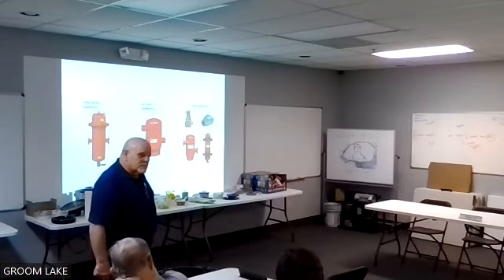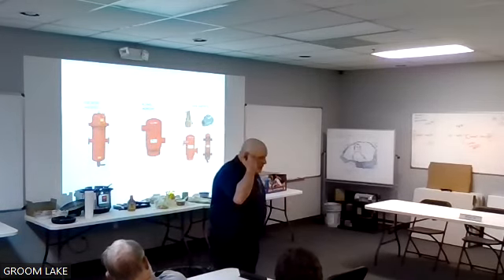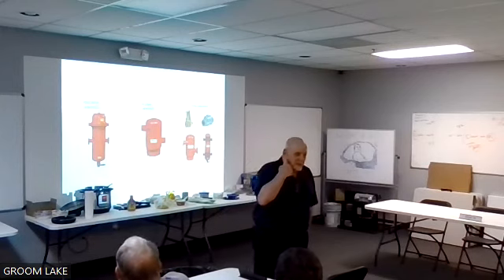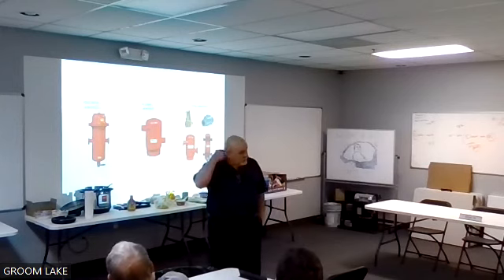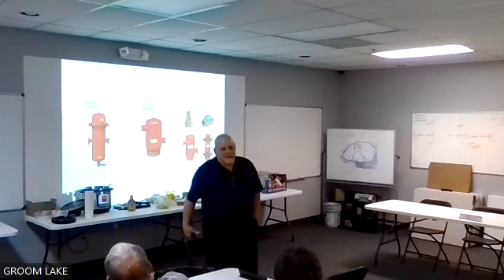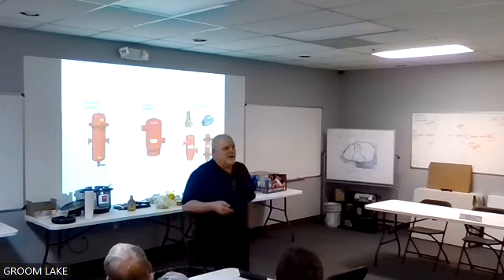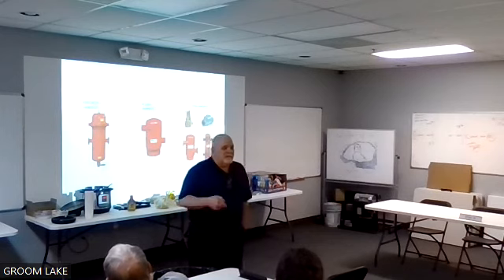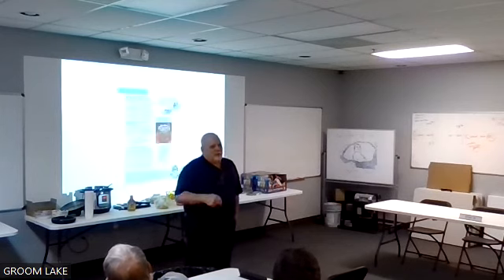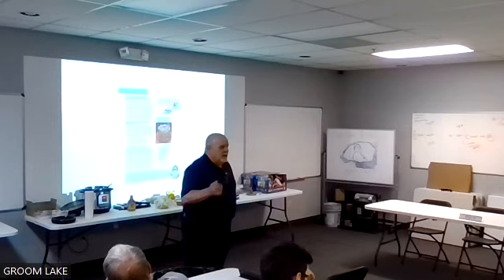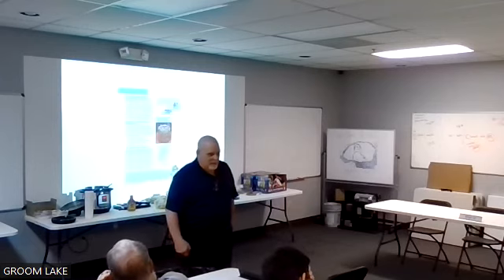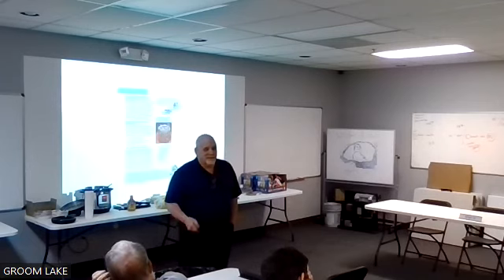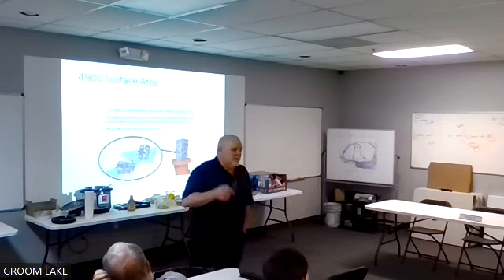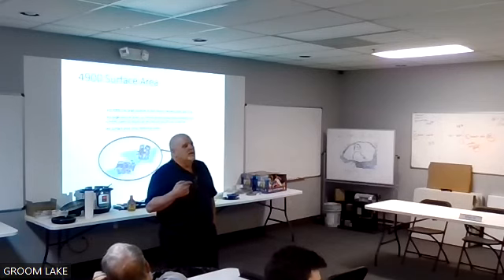It's a Taco flow through expansion tank. What's the purpose of those? Oh, I should have brought it up. That's a good point. I should have put that in my presentation. That's something fairly new. Taco just started building these flow through expansion tanks, and the big problem with domestic nowadays is Legionella. If you keep your water above 130, you're good. Legionella can't live over like 130, 140 degrees. Anything below 70 degrees, Legionella can't live. However, domestic water that runs 100, 110, 120 degrees is a perfect spot for Legionella. Plus your expansion tank is a dead leg of stagnant water.